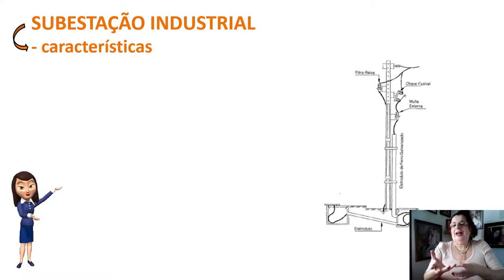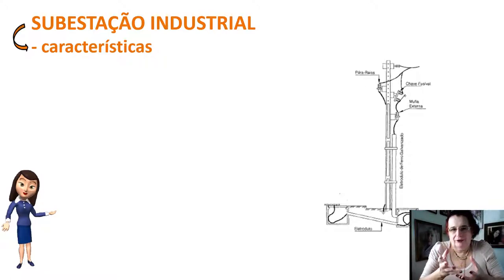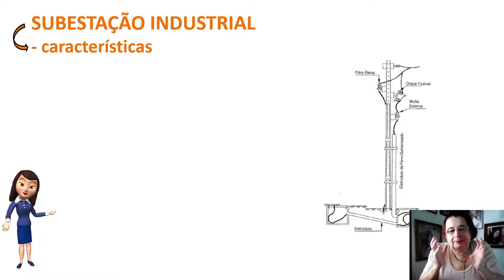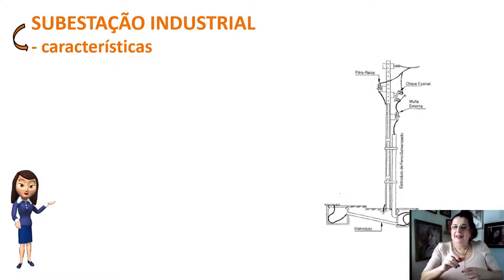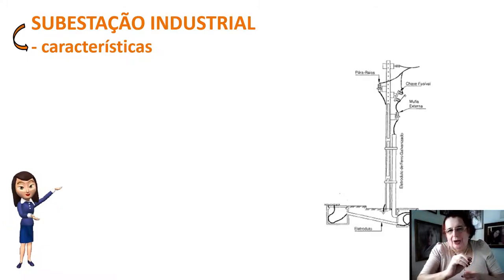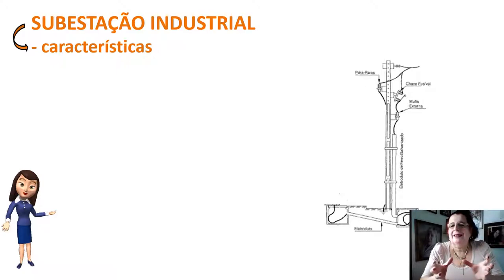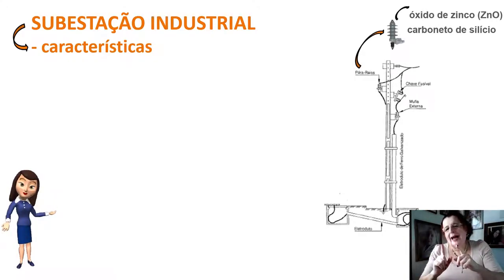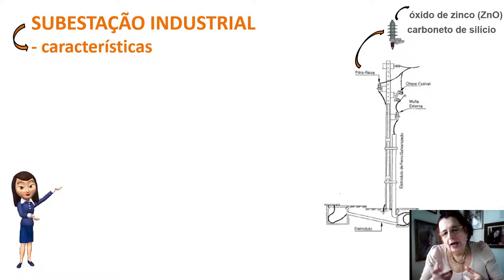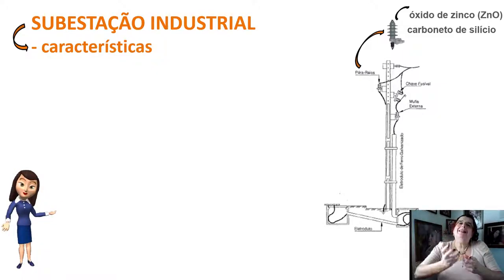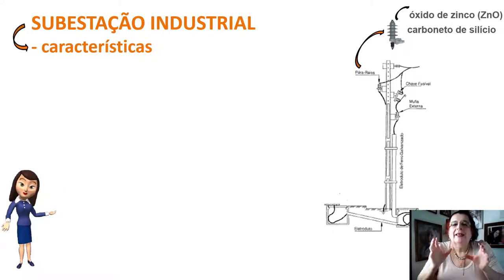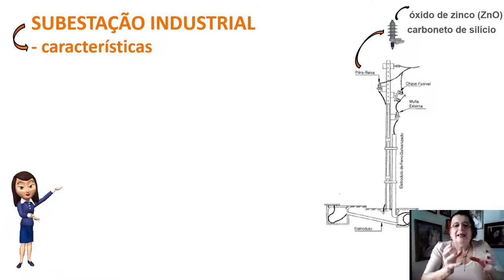As subestações industriais que recebem os 13 mil volts necessitam de características básicas para sua operação. O poste próximo à subestação industrial precisa de componentes de proteção, como o para-raios. Usualmente os para-raios são à base de óxido de zinco ou carboneto de silício, e sua função é drenar a elevada tensão provinda do arco voltaico do raio atraído pelos 13 mil volts da rede de distribuição.